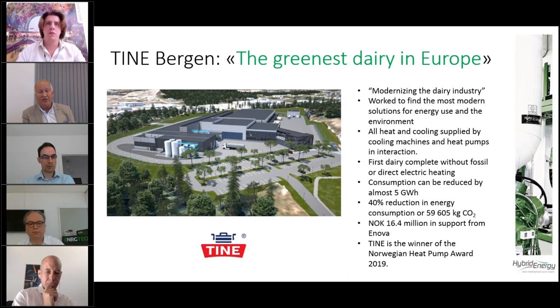The consumption can be reduced by almost 5 gigawatt hours annually, and a 40% reduction in energy consumption is expected, including 59 tons of CO2 emission reductions. The Norwegian support company Enova has supported the project with 16.4 million Norwegian kroner. Tine is also the winner of the Norwegian Heat Pump Award, given by the Norwegian Heat Pump Association.